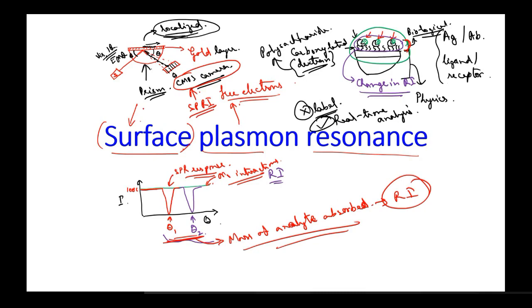Otherwise, if you think of a single detector, you would need to move it at different theta angles to capture the response. However, in the current day, because we have very sensitive CMOS camera systems and other different types of imaging systems, we can capture the spectral images at different angles in a single go. This reduces signal acquisition time and the complexity of the hardware of the system.